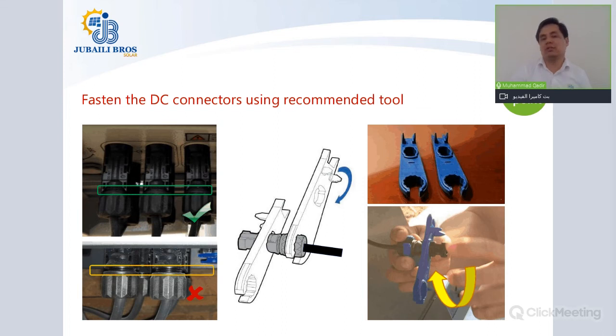If you are not using a proper tool for tightening the DC connectors, this will lead to loose connections, and a loose connection, as I said, can lead to sparking at the connection points. So I highly recommend that you use DC connectors from the manufacturer, both from Amphenol and from the MC4.